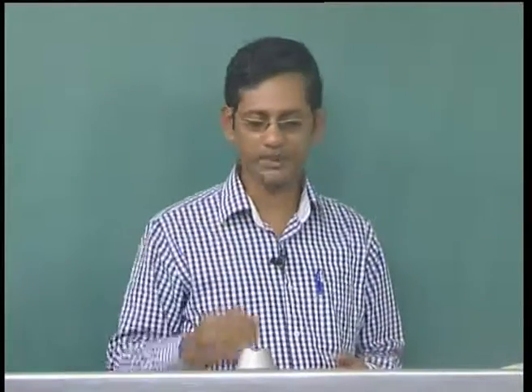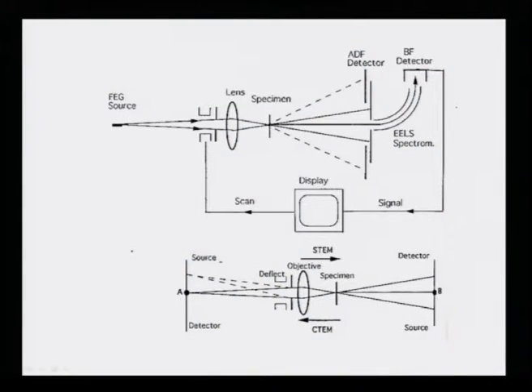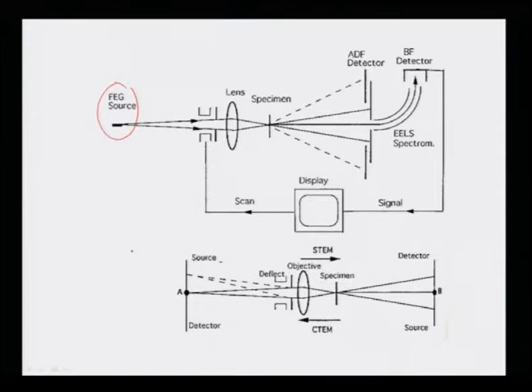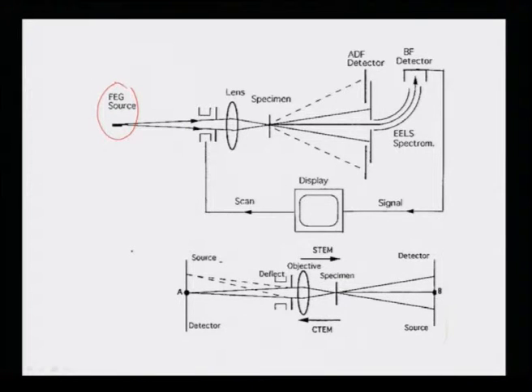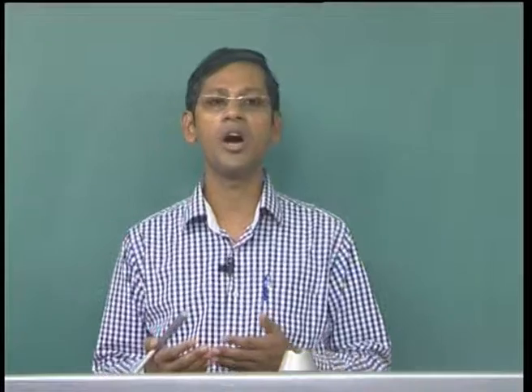In a scanning transmission electron microscope, we have a field emission gun (FEG) source of very high brightness and small energy spread. This FEG source is focused by the objective lens onto the specimen, demagnifying the electron beam into a convergent beam. When this convergent beam falls on the sample, it diffracts and gives diffraction discs from both transmitted and diffracted electron beams.